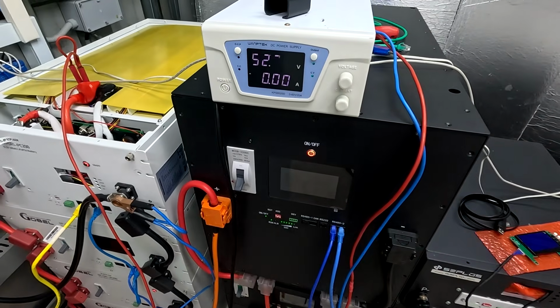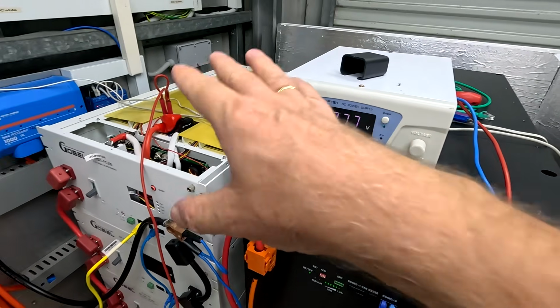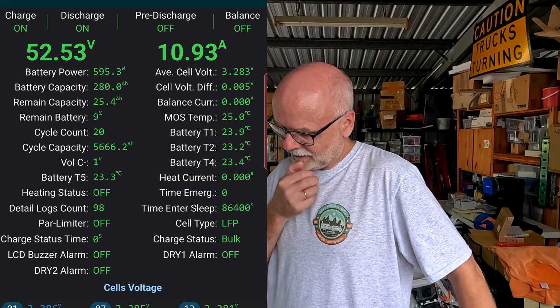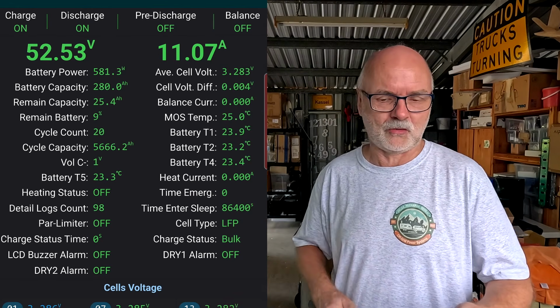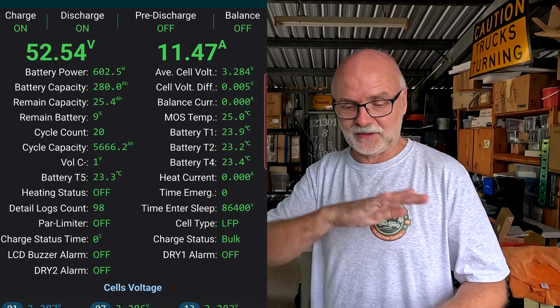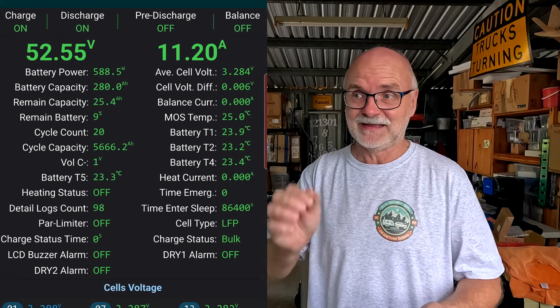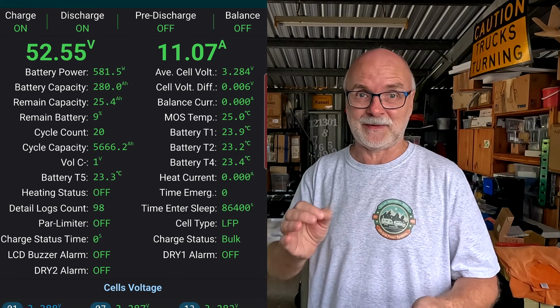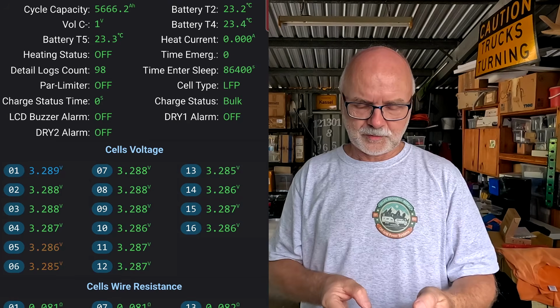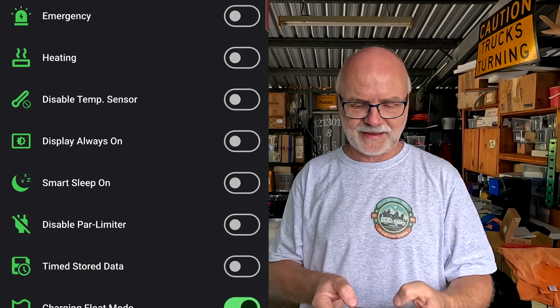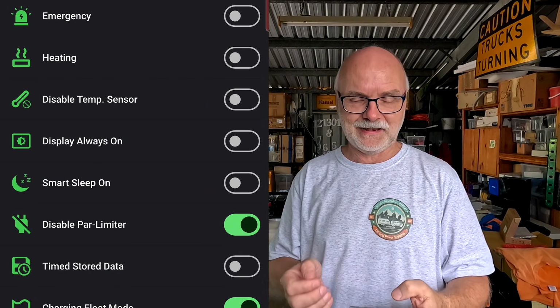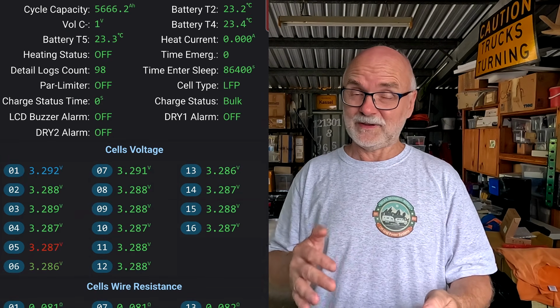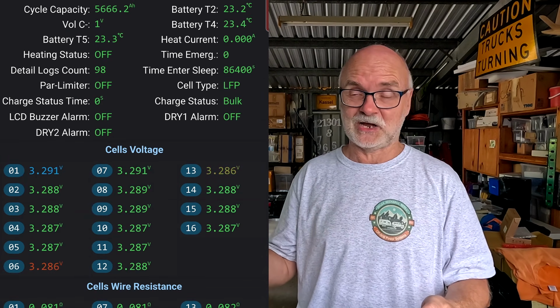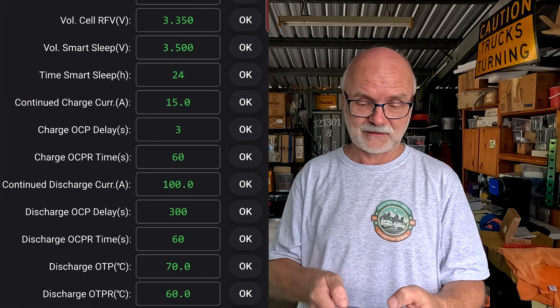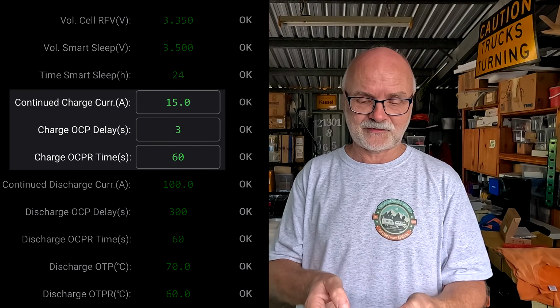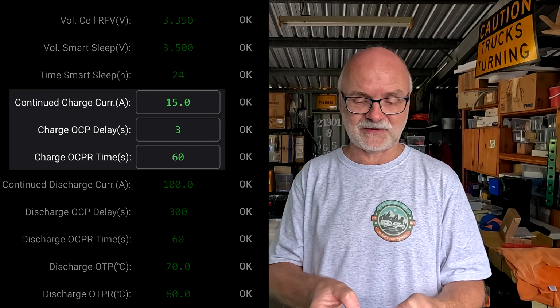So when I turn this on here, we're obviously charging now with 10 amps into this battery. And here the BMS in the app shows us also 11 amps going in, yeah? So there's no problem at the moment, but we have set the maximum charge current for this BMS to 15 amps, yeah? What we are going to do now is we are disabling the parallel limiter. That means when we hit the 15 amps maximum charge current for 3 seconds, yep, there it is, 15 amps, continued charge current for 3 seconds.